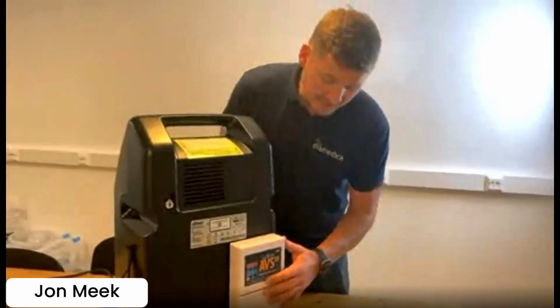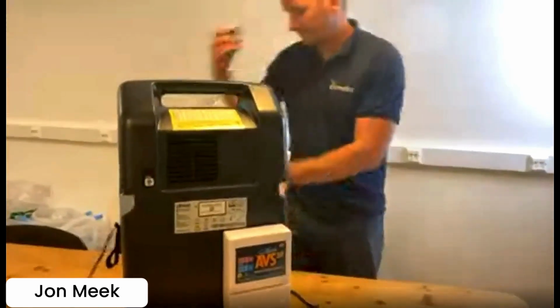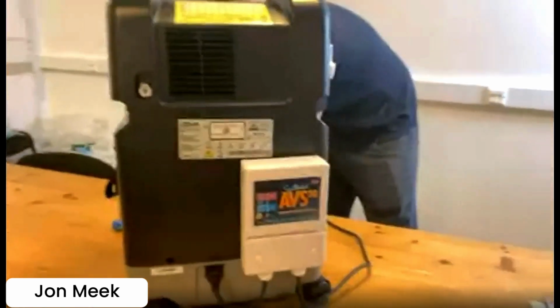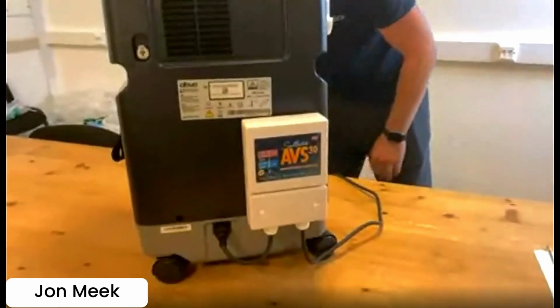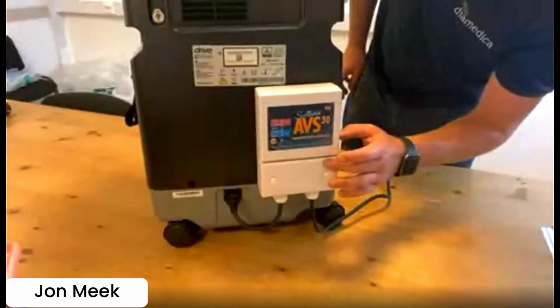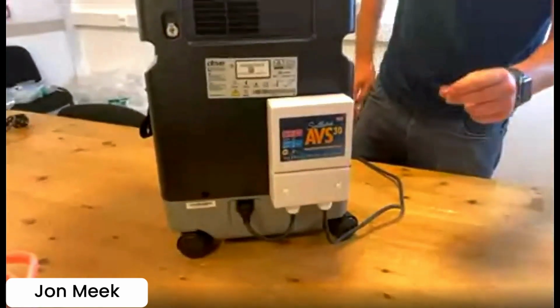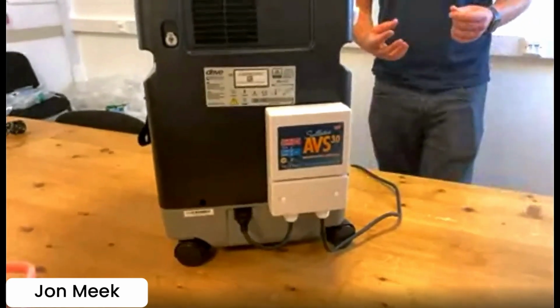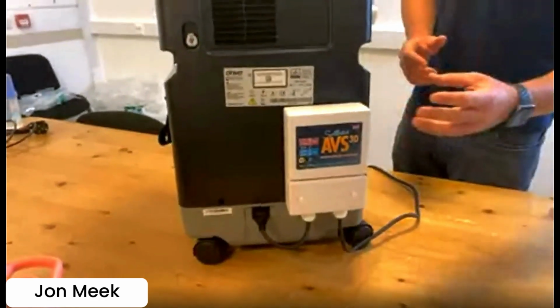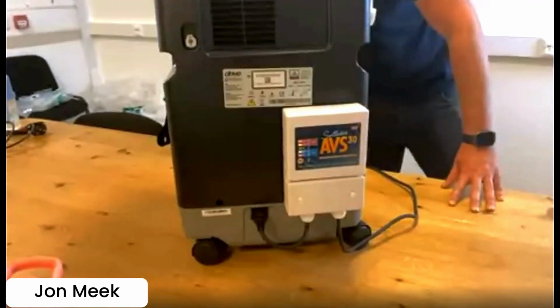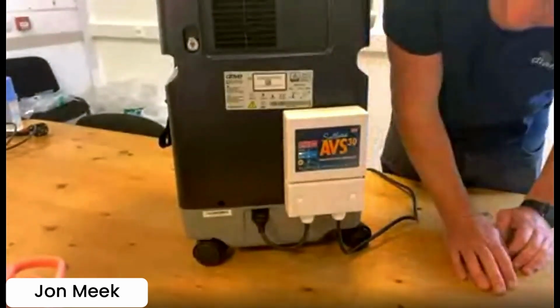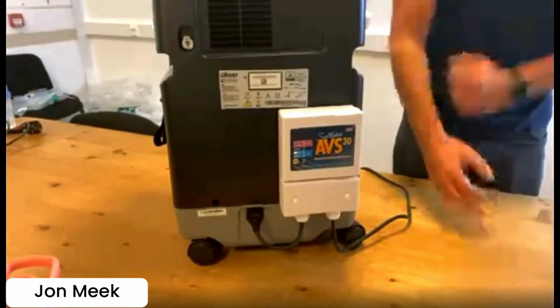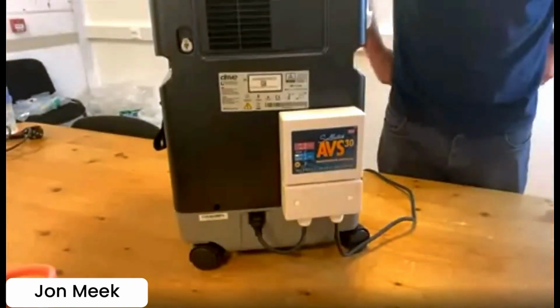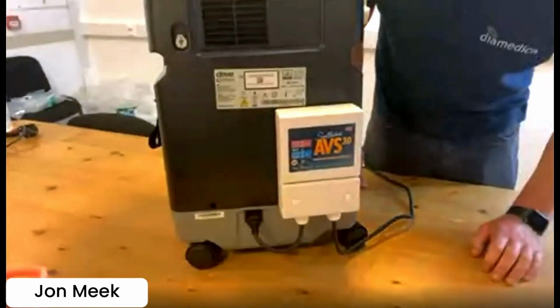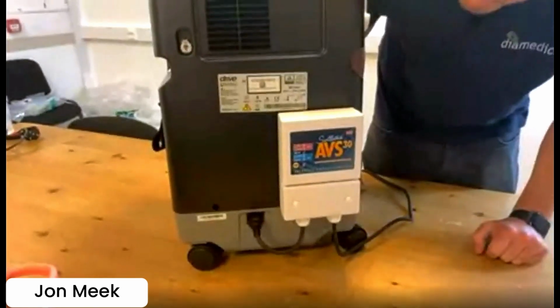It does, again, a self-test. If I plug this in, you'll see all 3 lights illuminate on the machine, and then you'll see it go orange. This orange means it's analyzing the voltage for that 10 seconds, and then it will go green, and that means it's safe to use. So if I plug it in, it's now orange, which indicates the voltage is good, but it's just analyzing it for that 10 seconds to ensure it's steady. And now it's gone green.